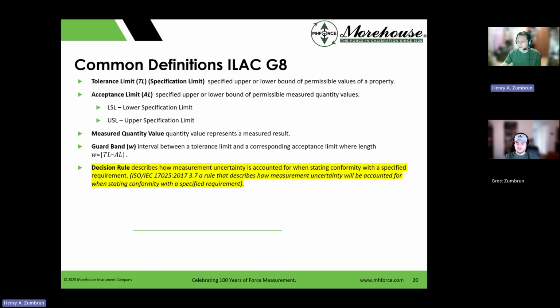And if we draw this out, there's lots of stuff there to think about. There's my tolerance limit, right? This is the manufacturer spec, or somebody else might have raised the manufacturer spec. They're telling you something for the measured point. The acceptance limit is basically, hey, there's a level of risk I can live with. Calculate this out so my PFA is less than 2%. They could say 5, but typically most standards are written to say 2. And then I have a measured value there.